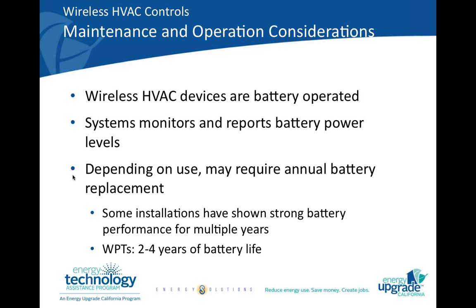So as I mentioned before, there are some maintenance and operation considerations and benefits from both of these technologies. First, both of these devices are battery operated. The system will monitor and report battery power levels, and when a battery runs out, you'll know and be able to replace it. Depending on the use, the batteries might last a year, multiple years. It really depends on how they're being used. For WPTs, for example, they guarantee at least 2 years, if not more, of battery life based on operation. Next slide, please.